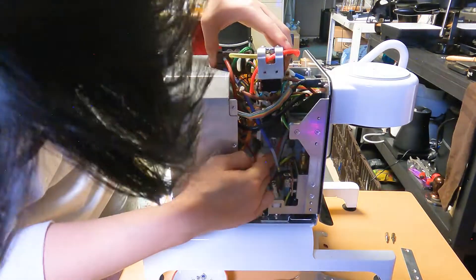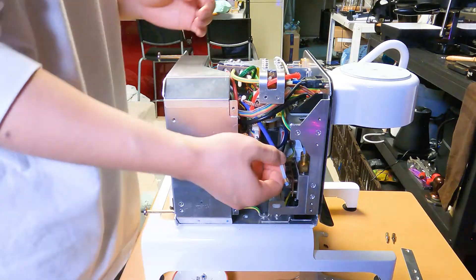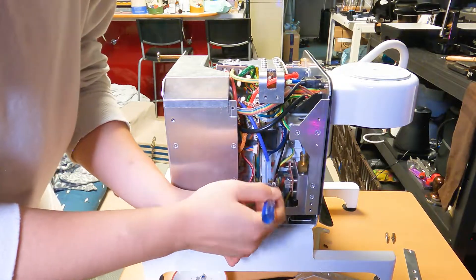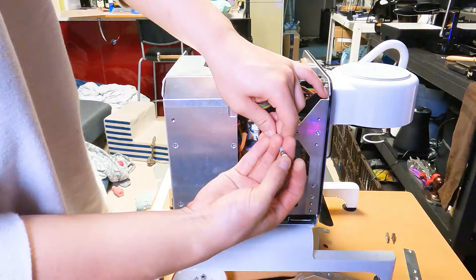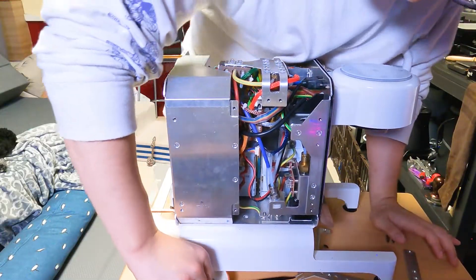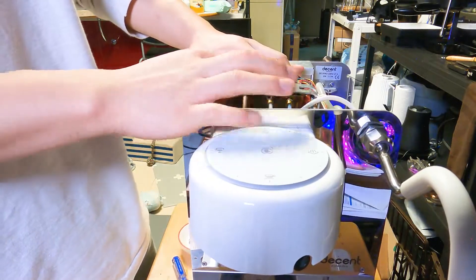Now this tube goes on the valve — just push it in, easy. Then the purple one — there is an O-ring inside the over-pressure valve. Put the tube on and push it in, wiggle it a bit, then put the clip in.